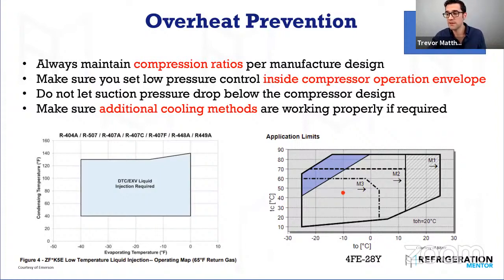The one on the right side is a Bitzer operation envelope. And this is what you need to start understanding: where's the system running inside these envelopes? Because if you don't, and it's running outside, like putting the low pressure control, setting it for 1 PSI or 5 PSI or half a bar, and your compressor's limit is higher than that, you don't want to go lower. Sometimes you don't want to go lower than 1 bar in that compressor. You're outside the envelope, or at 15 PSI, that means you're running outside the envelope.